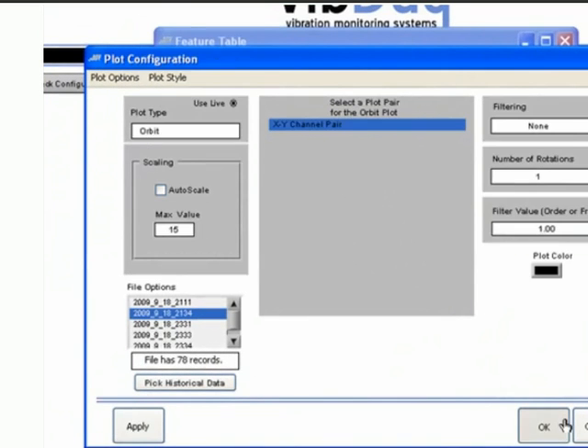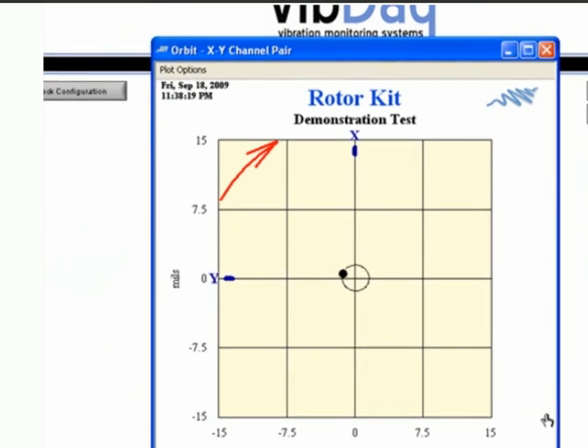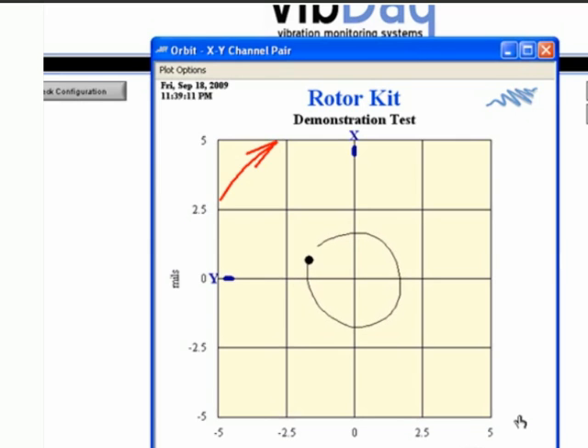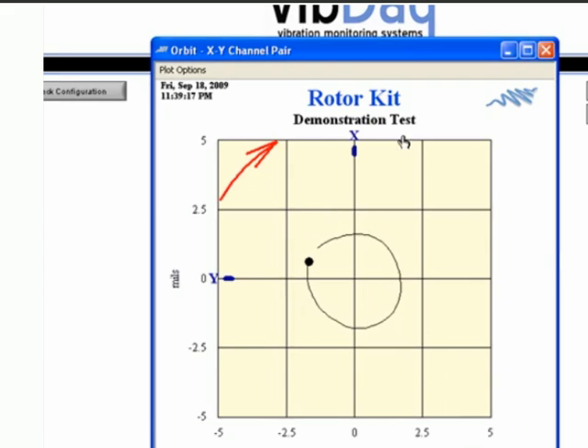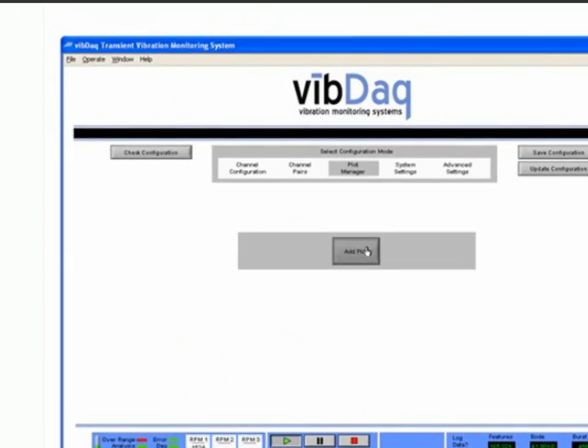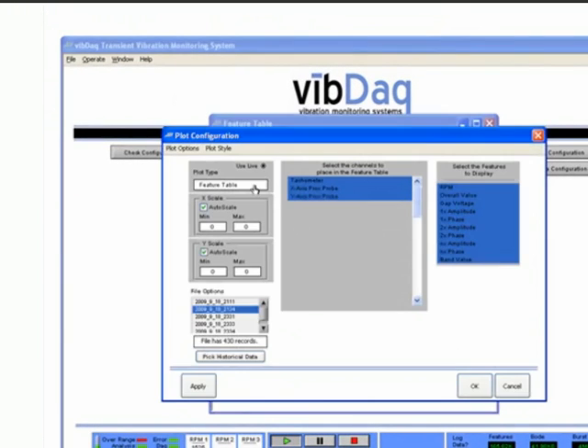Orbit plots show data from a channel pair. Channel pairs are made up of two sensors mounted at the same point along the length of a shaft, but at different angles. By combining their data, you can illustrate the position of a shaft over the course of one or more rotations. Specific travel patterns can be indicative of certain types of problems, such as bearing wear or shaft rub.